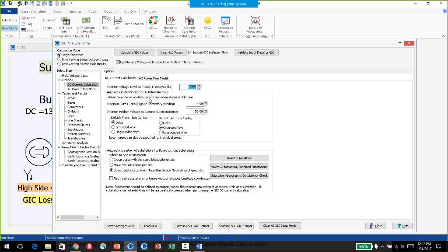So this idea that for anything below 200 kV, why bother, just say it's unavailable, there is no GIC, is a terrible idea. That's something we have to feed back based on testing in the field, so to speak, from doing the analysis. I think it originated from when people started looking at this issue, before we started putting these tools into the software. Now we did it first, Tom did it first, and then PSSE and GE PSLF have the tools now, everybody has the tools.